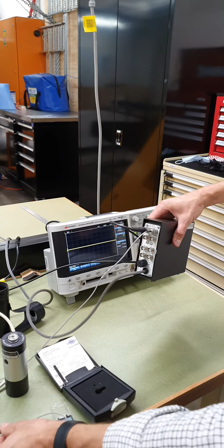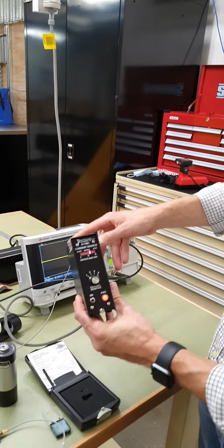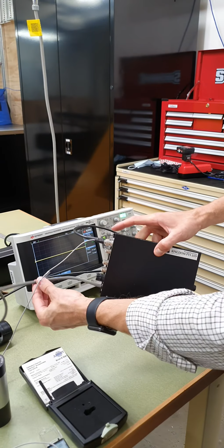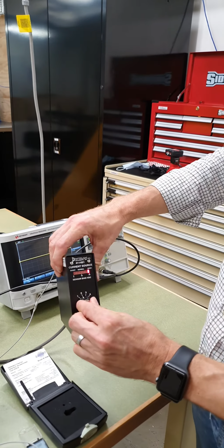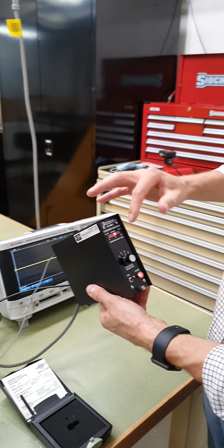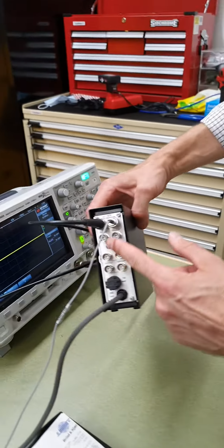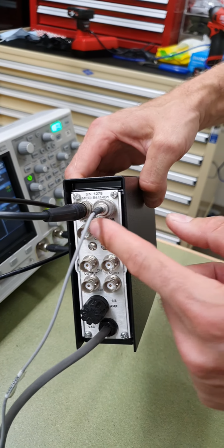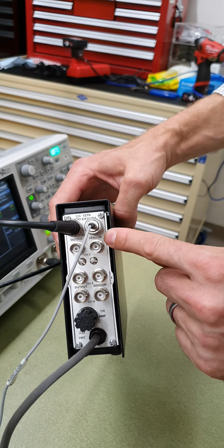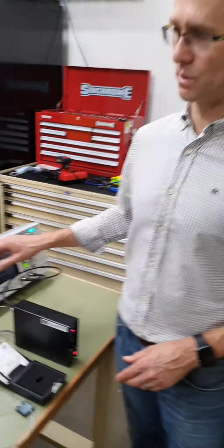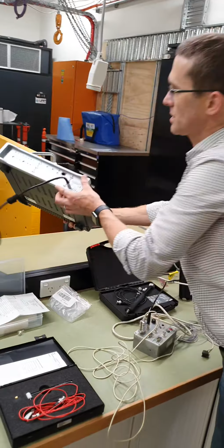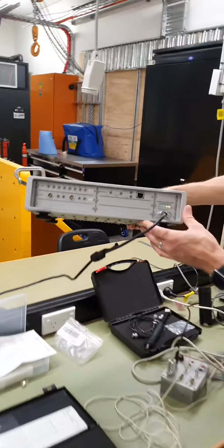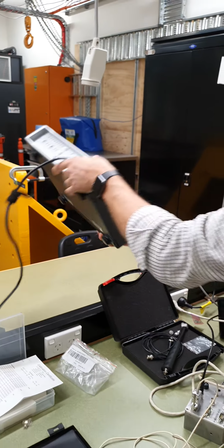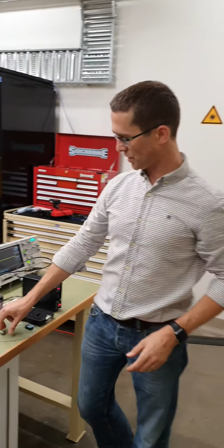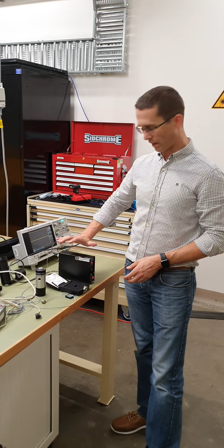Okay. In terms of the power supply, this is a 4-channel IEPE power supply, which is powered by mains, plugged into 240 volts. We've got 4 different channels on here, and we can select between them to check the functionality of the channel, and each of the 4 channels is captured in a pair of BNC connectors here. So this one goes on the right, goes to the sensor, and this one goes to the measurement system, which is an oscilloscope. Some other types of measurement systems, for example, this Siemens SimCenter SCADAS mobile acquisition system, which I'll describe in a subsequent video, have IEPE signal conditioning built in, so we can use these transducers without this intermediate signal conditioning supply in that case.